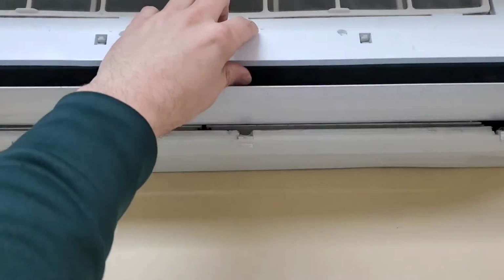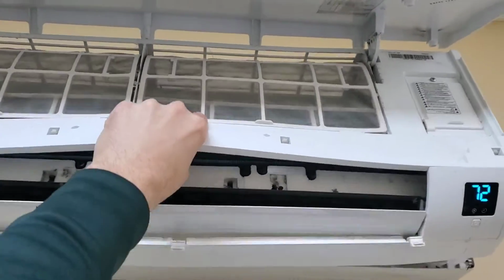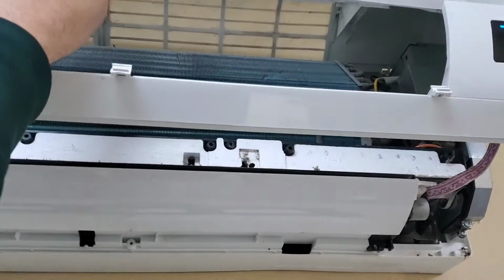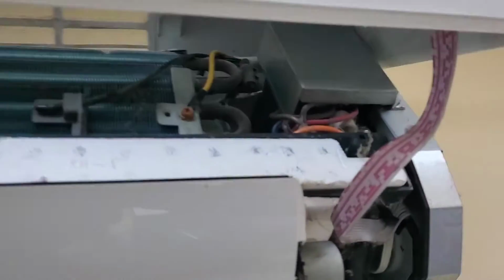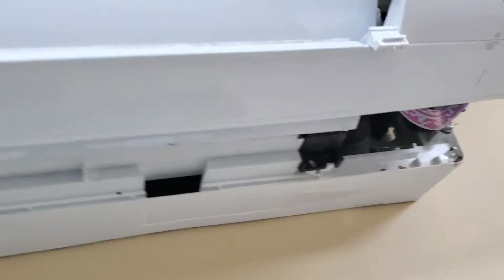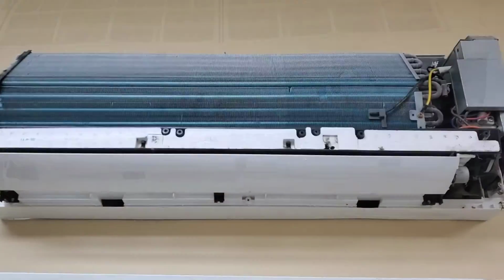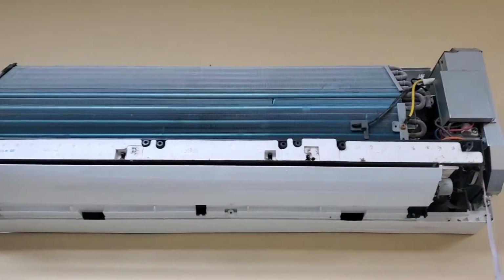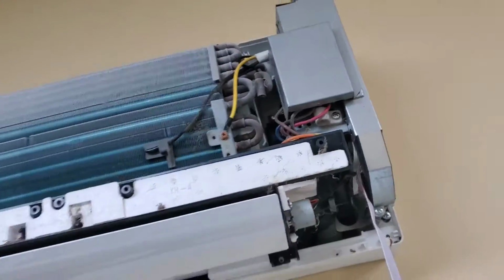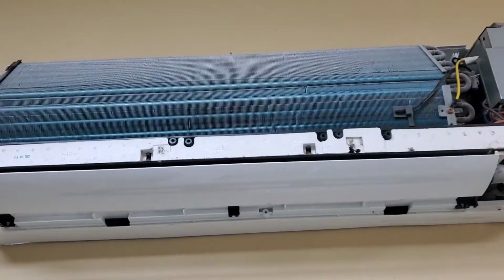All right? See, I'll show you. See, it's all loose, ready to go. Take it right off. Make sure that you unplug this. All right, it goes to the display. This is a little plug that goes back to the PCB. You need to unplug that, guys, okay? And then you take this off. All right, so once the front cover is off, then you'll be able to get to the control board over here so that you can make your checks to make sure the motor has power when it's calling for the indoor motor to spin.